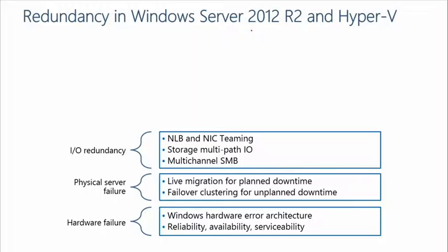If you're running Fibre Channel, it's glass cable. It has a bend radius before it breaks. If someone is running cable and they just kind of jam it a bit and kink it, you get a cable failure. So I/O redundancy is really built around cable and path failures, or potentially switch failures in the middle. Switches don't fail often, but when they do, they fail very spectacularly.